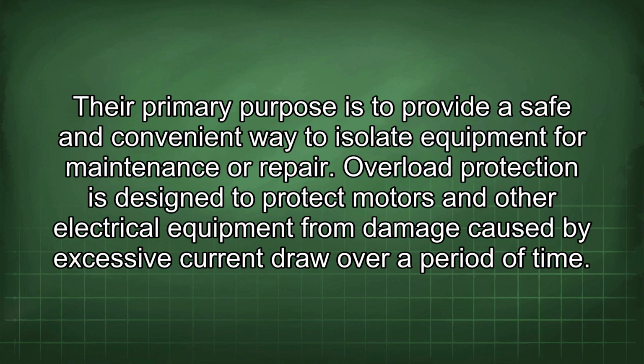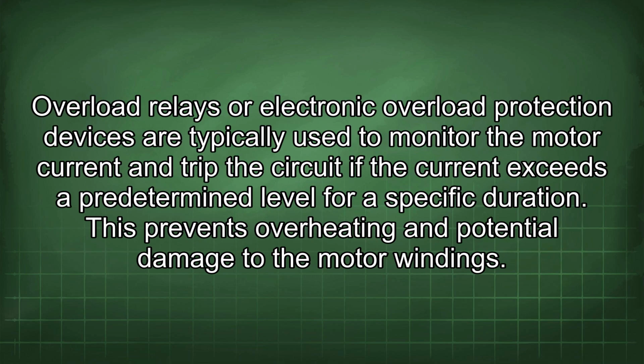Overload protection is designed to protect motors and other electrical equipment from damage caused by excessive current draw over a period of time. Overload relays or electronic overload protection devices are typically used to monitor the motor current and trip the circuit if the current exceeds a predetermined level for a specific duration. This prevents overheating and potential damage to the motor windings.